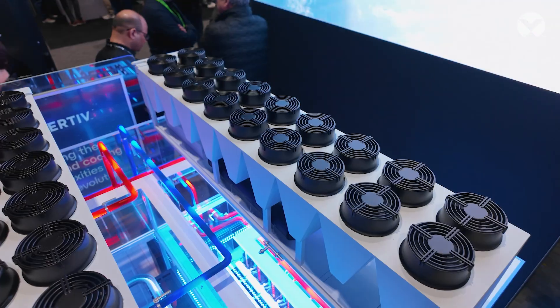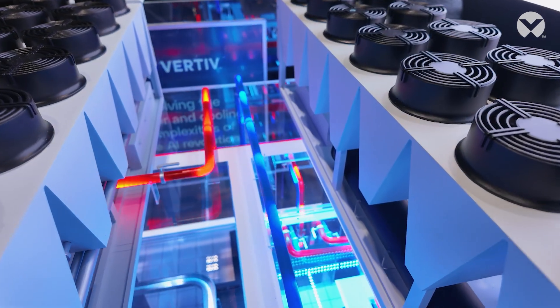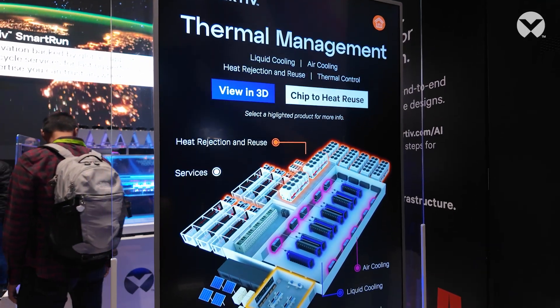The first one is how to continuously cool the GPUs. The liquid is going from a coolant distribution unit to the heat exchanger on the chip, removing the heat. What we found was we've got to keep that cooling continuous. If you're thinking about continuous cooling, you've got to power protect the equipment that's forcing that liquid cooling.